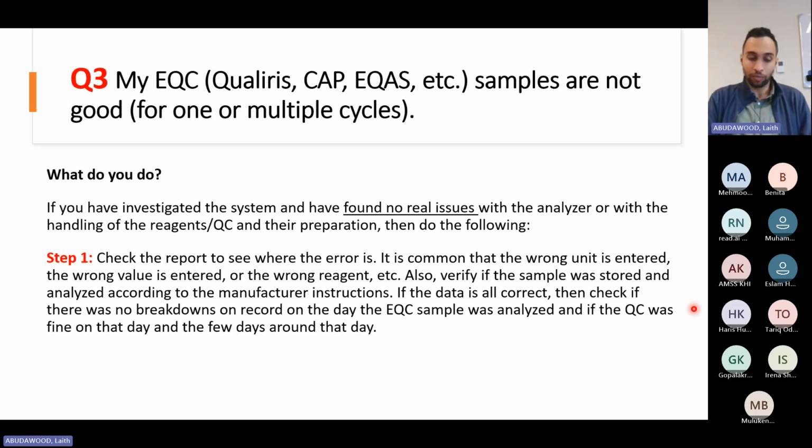And that was the case. So please make sure to check this point, because you will notice more than once in your career, for sure, that it is simply that the customer forgot to do something or did not do something properly as the manufacturer of this external quality control has requested. So always make sure to check that, otherwise you will go into a bit of a deep investigation. So to avoid deep investigations, which are absolutely pointless, check this first, then we can move into next steps.